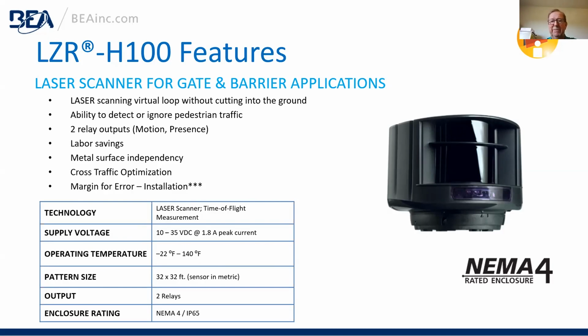Now, that may be covered in this slide, but we'll cover it now. If you look at the bottom of the sensor, this is 2 pieces. This bottom narrower portion is actually a second piece, which is the base. When the two go together, if you look at the bottom of the laser, it actually has a cover that snaps on over the electrical connection. So it's absolutely critical, when you plug the wiring harness into the base of the sensor, that you plug that plastic cover on, and it has to snap.